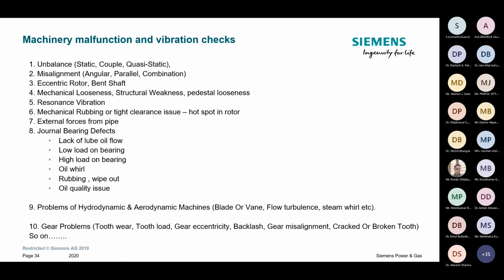Like we all know, it's lubricated by an oil film, an external oil supply. Now oil quality, oil temperature, oil type, all this impacts my rotor dynamics, and I will see vibration there. Sometimes you will see bearing temperature start increasing, or certain temperatures going down and certain temperatures going up. You will see erosion in the bearings itself, because of alignment the bearing tries to get low. These are relative things.